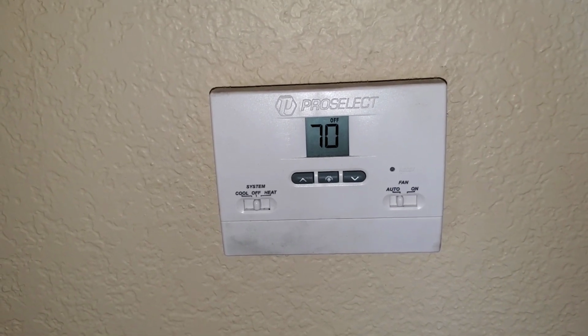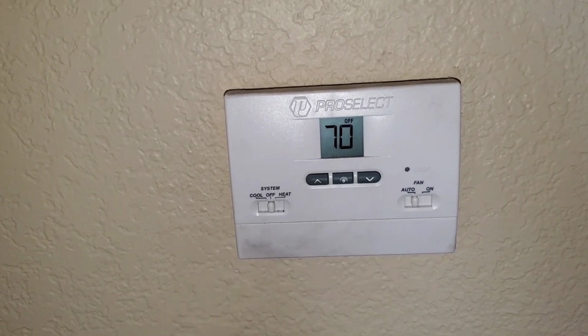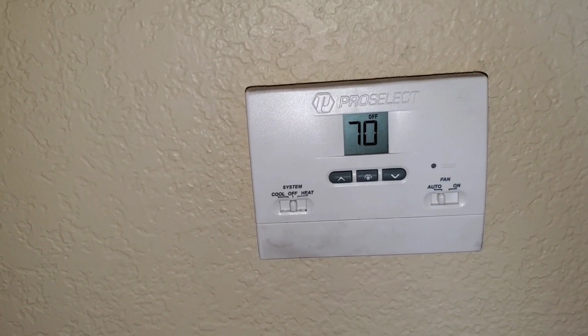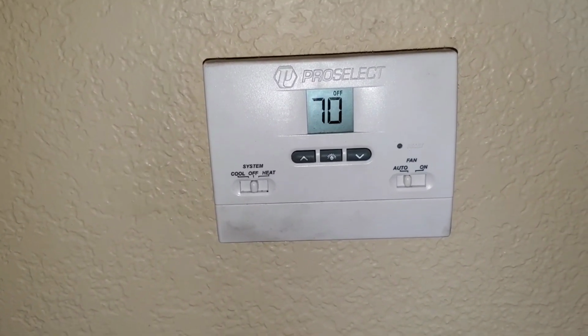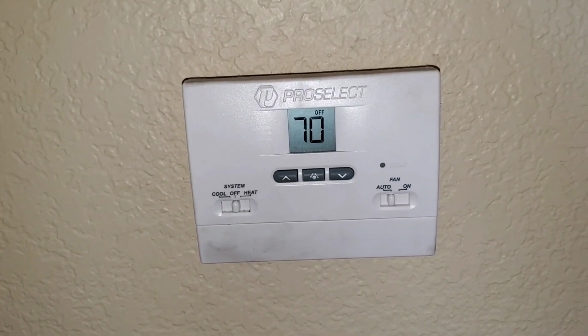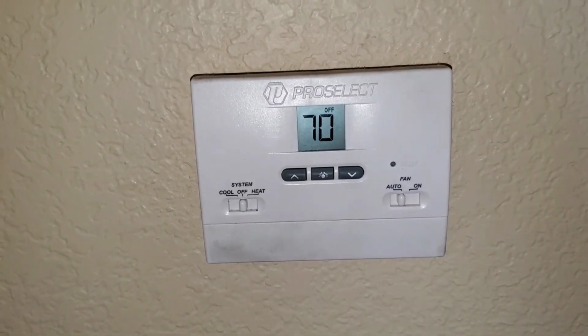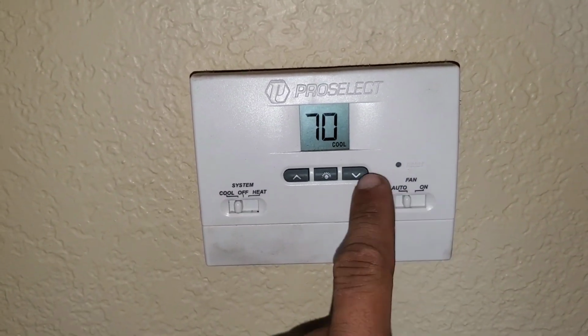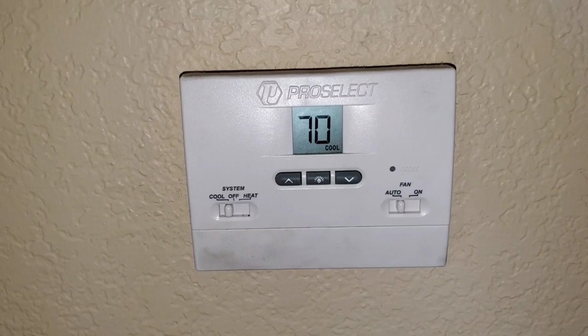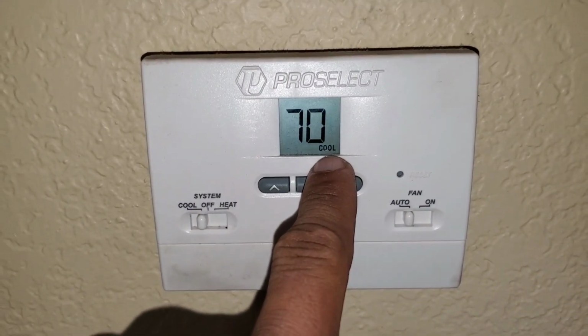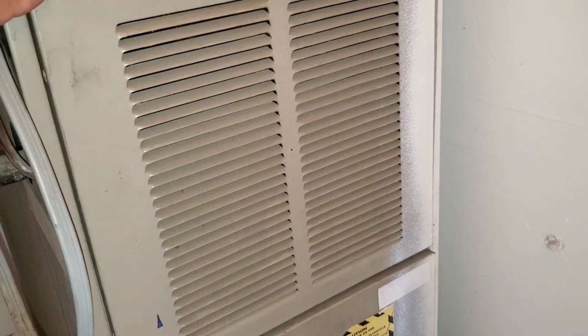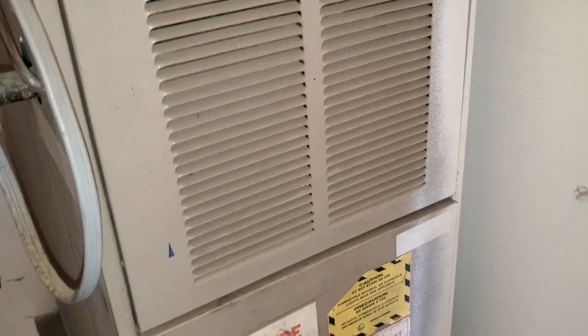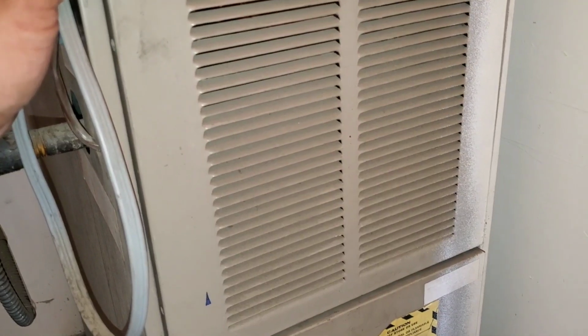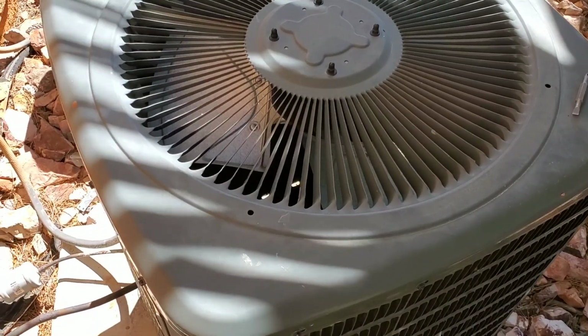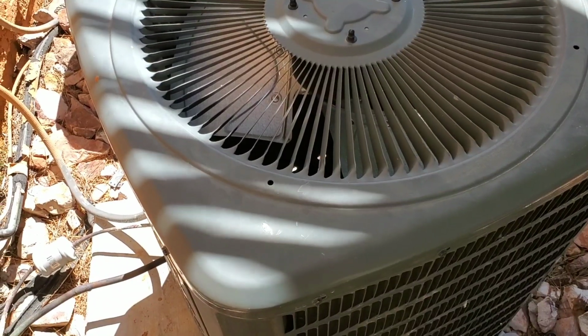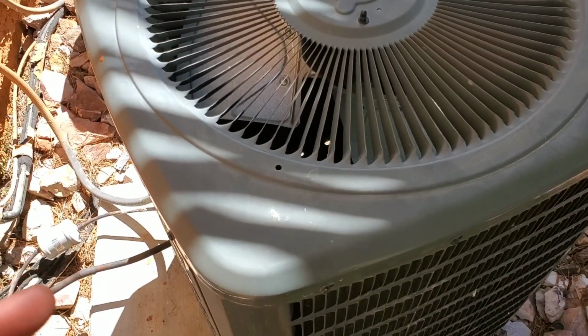Right now, we're going to start the troubleshooting process. Again, these are just some basic calls to give you a foundation when you start into the industry and to systematically troubleshoot your system in your mind. So right now, we're going to start at the thermostat, set it to cool, set it to auto, and drop the ambient temperature. Right now, my thermostat is calling for cool. Now we're going to go to step number two. Step number two, we're here at the return. The blower did not turn on. So here, we wouldn't go to step number three, obviously, because we know we're having issues between step number one and step number two. This is just a tip or a trick to throw in there.